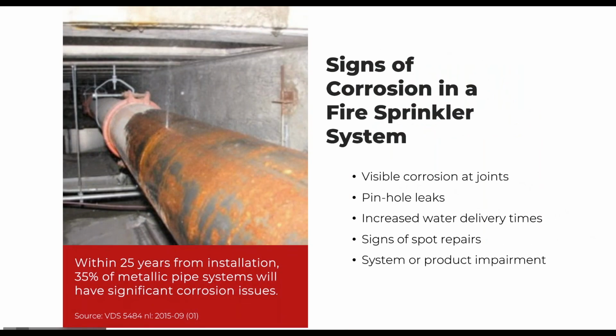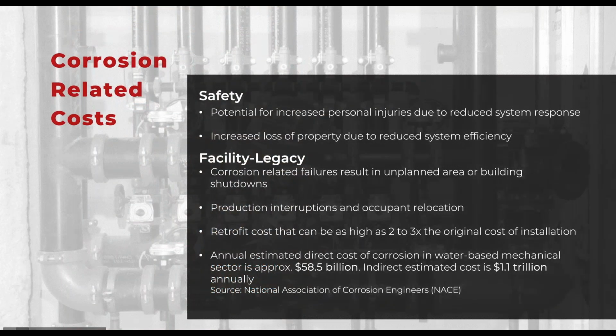And when we say effects, some people think, well, how do I know if my pipe's corroding? It could be as simple as just seeing a pinhole leak. That certainly is a sign the pipe has had a major corrosion failure event, up to catastrophic failure like I described. And what we're seeing in the industry is that fire sprinkler pipe is not lasting as long as we had initially thought. It could be an issue with people using thinner and thinner pipe to do jobs. It could be a variety of issues, but a long-term study was done, and we're seeing that about 35% of wet systems are failing within the first 25 years of their life. So that's certainly a concern.